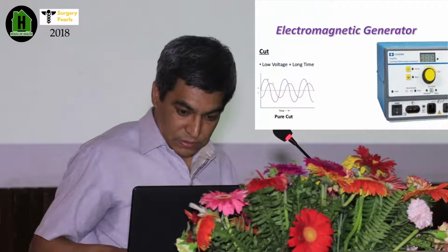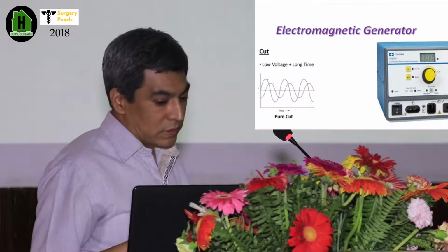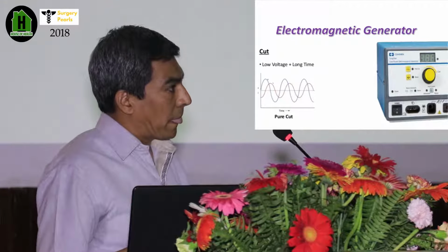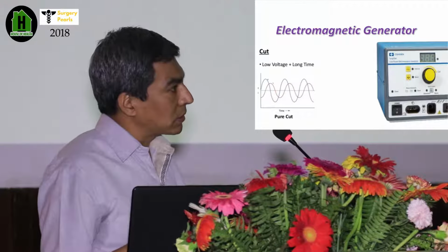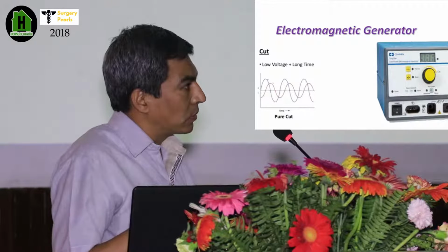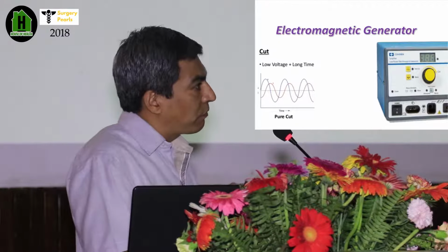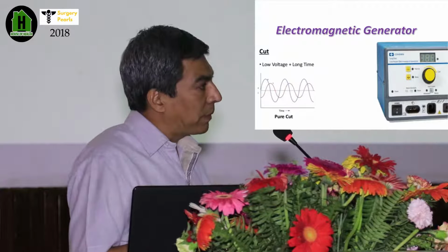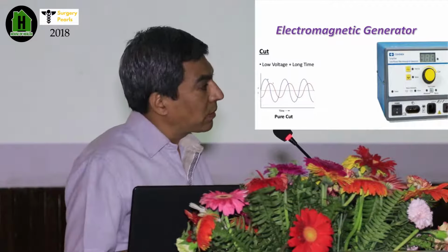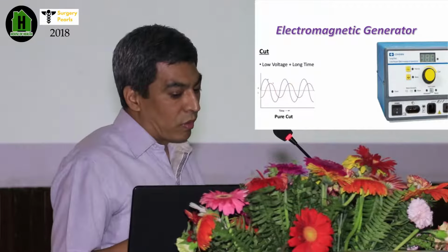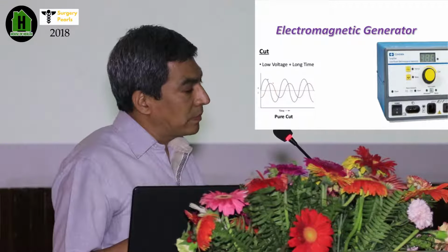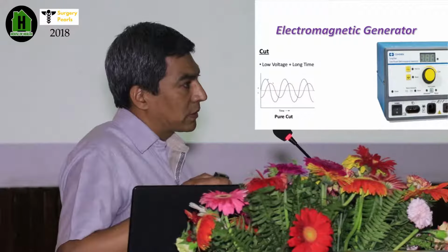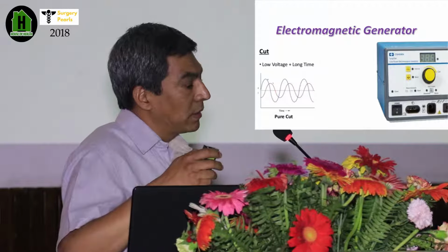On the other hand, if you go to the coagulation mode, the voltage will be very high, and it is not continuous. It is in pulses. It comes and goes, and that will be for a short time only. So what will happen? In case of cut, there will be very low voltage, and it takes a long time, and the energy will be increasing one after another, higher and higher, till there is enough energy to explode the cells. So it will give the cutting effect at the tissue.